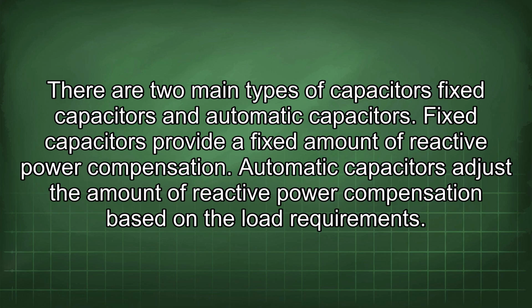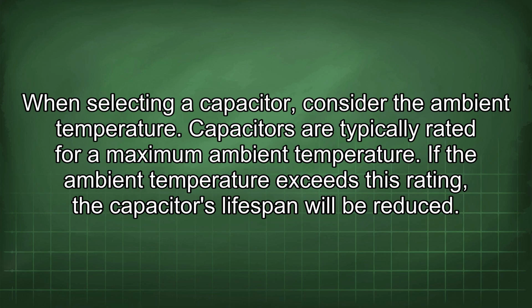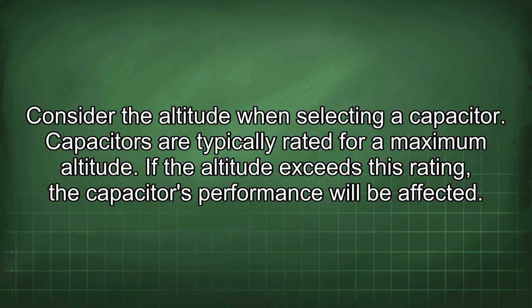When selecting a capacitor, consider the ambient temperature. Capacitors are typically rated for a maximum ambient temperature. If the ambient temperature exceeds this rating, the capacitor's lifespan will be reduced. Consider the altitude when selecting a capacitor. Capacitors are typically rated for a maximum altitude. If the altitude exceeds this rating, the capacitor's performance will be affected.